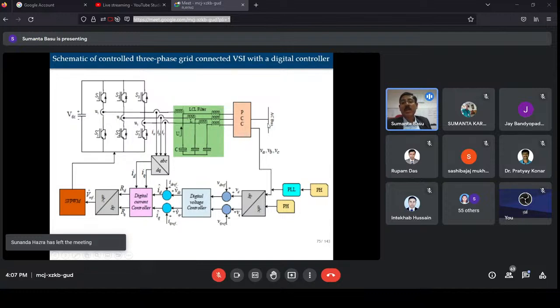This is a practical schematic, but not for a very large-scale utility, as I already told, this is for a microgrid. This is working, but when those microgrids are connected to the main power systems, a lot of other factors also need to be considered. The instance on 11th August that I had shown in my first slide was on a large scale. So what happened, as you have seen, is that these types of algorithms to take care of sudden load change and sudden frequency change have not been applied, because that is not available yet. More and more research is going on to apply them in practical aspects.